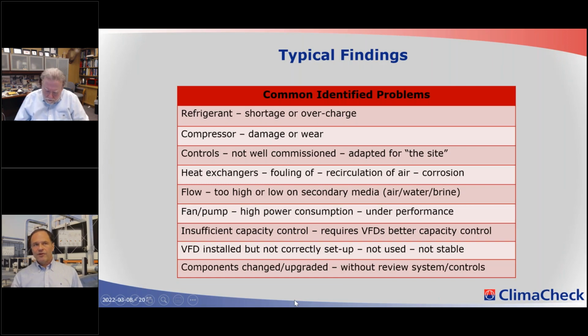And an air conditioner refrigeration system is quite complex, even though there are not that many components. I mean, we only need 10 sensors to evaluate the process. But there are quite a few things that can go wrong. And unless you have good measurements, it can be challenging to identify what is wrong.